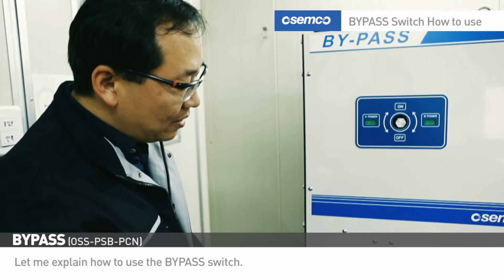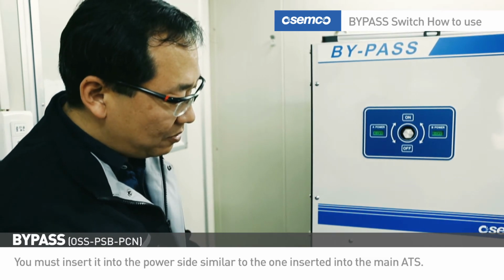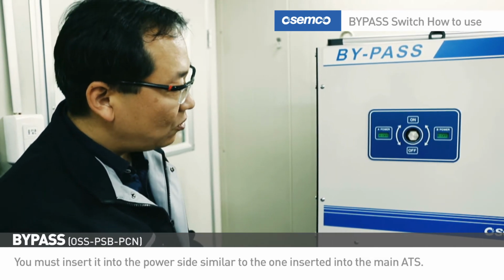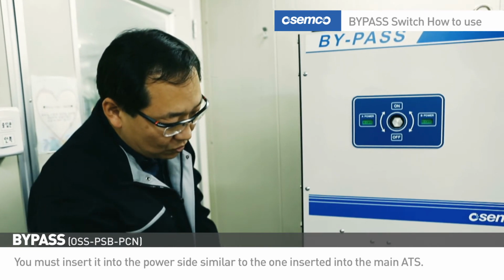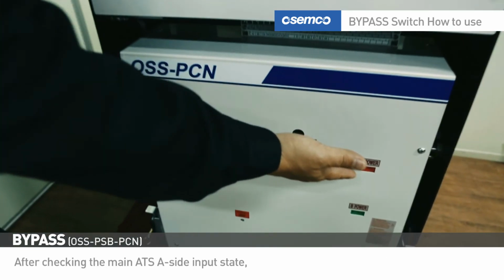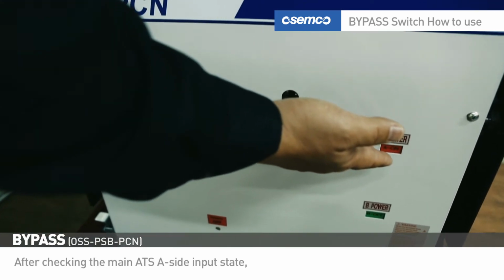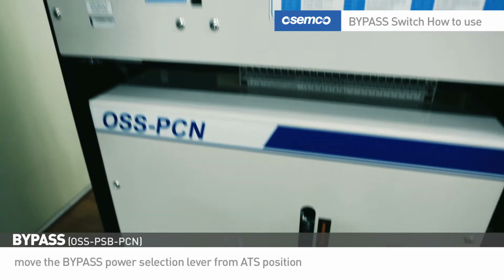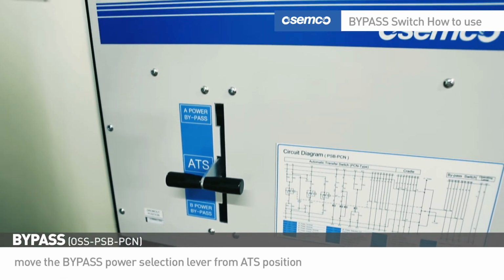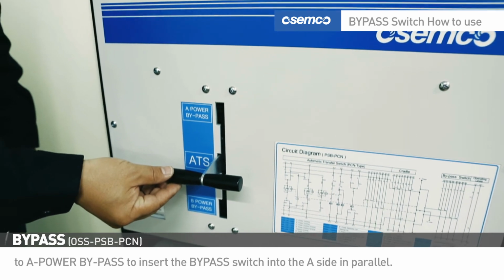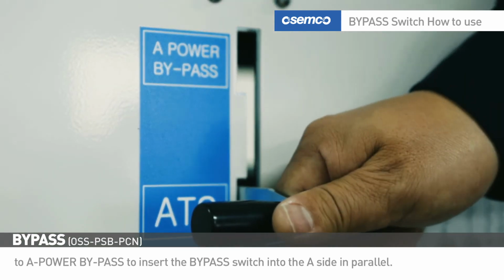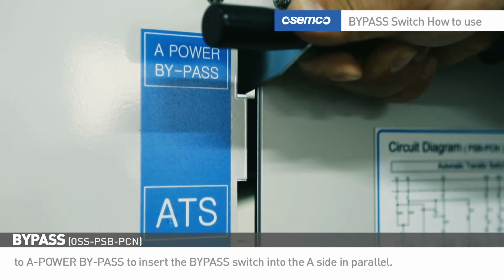Let me explain how to use the bypass switch. You must insert it into the power side similar to the one inserted into the main ATS. After checking the main ATS A side input state, move the bypass power selection lever from ATS position to A power bypass to insert the bypass switch into the A side in parallel.